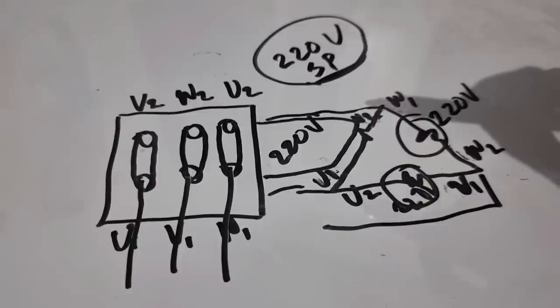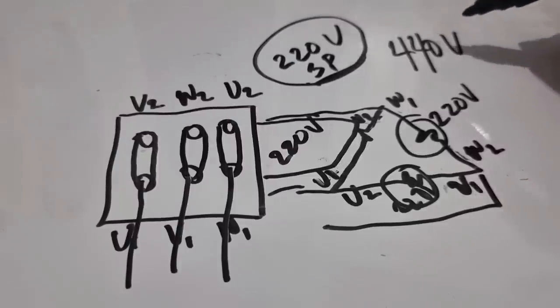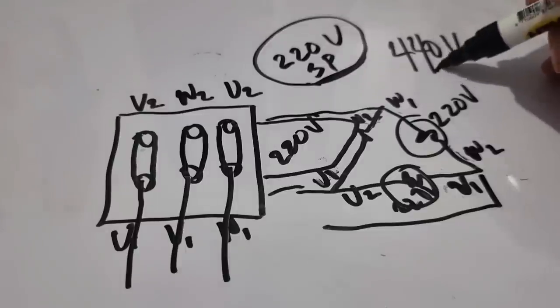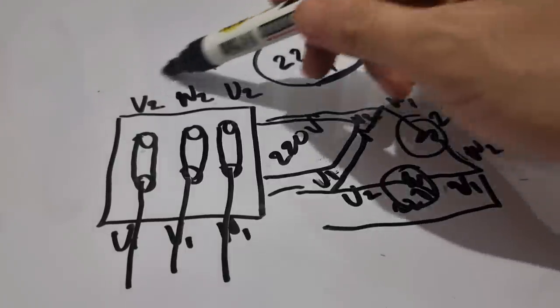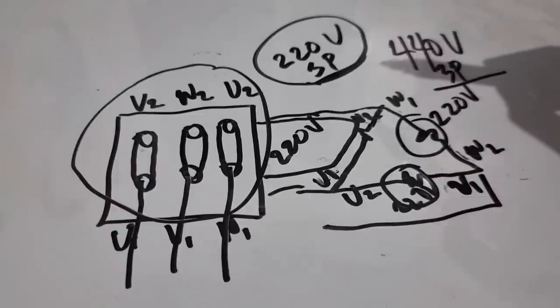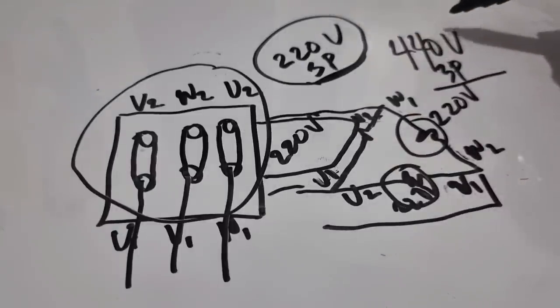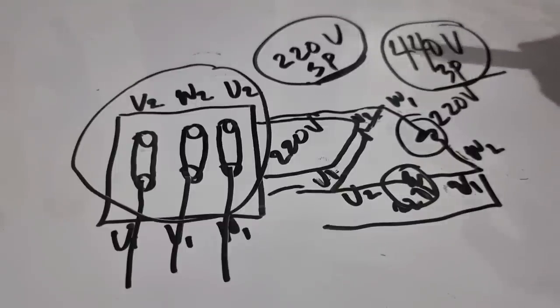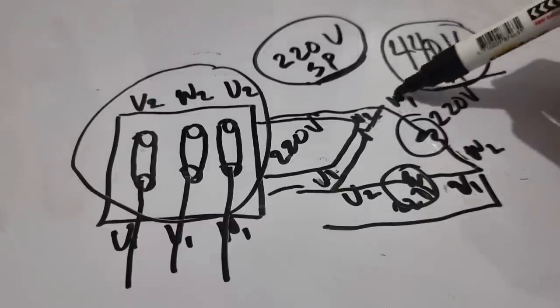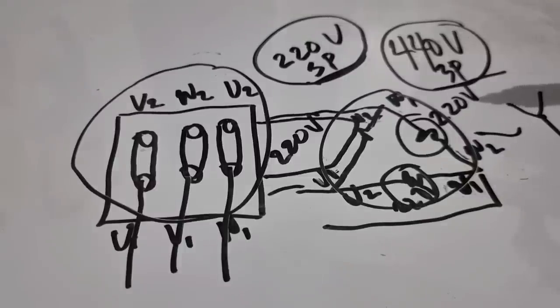The idea is we have a 440 volt supply on the vessel with three-phase. So the current connections of the motor — I am going to change these connections to be able to use the 440 volts. How are we going to do that? I will convert the delta connection into a Y connection, and I'll explain how it will be possible.